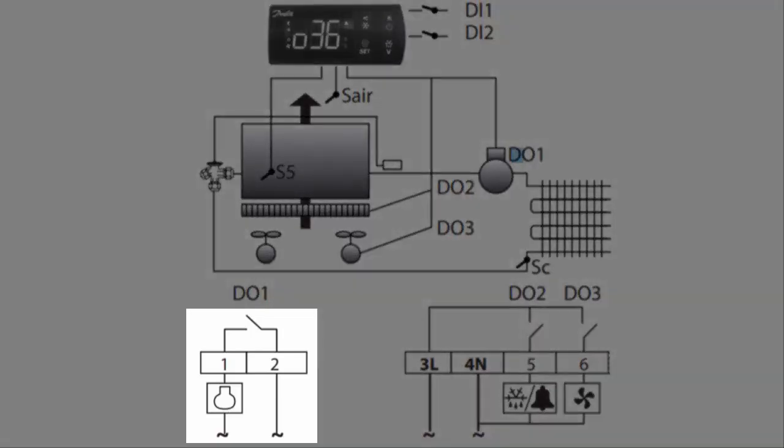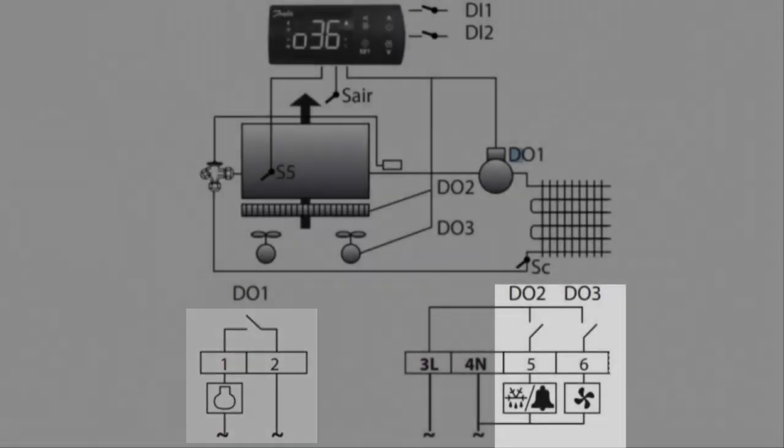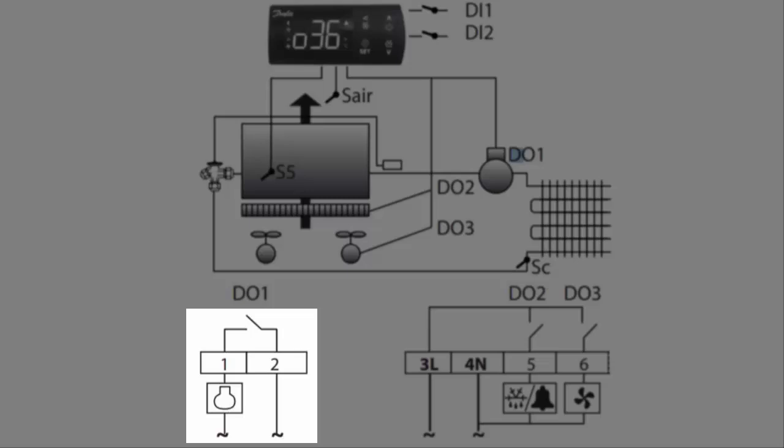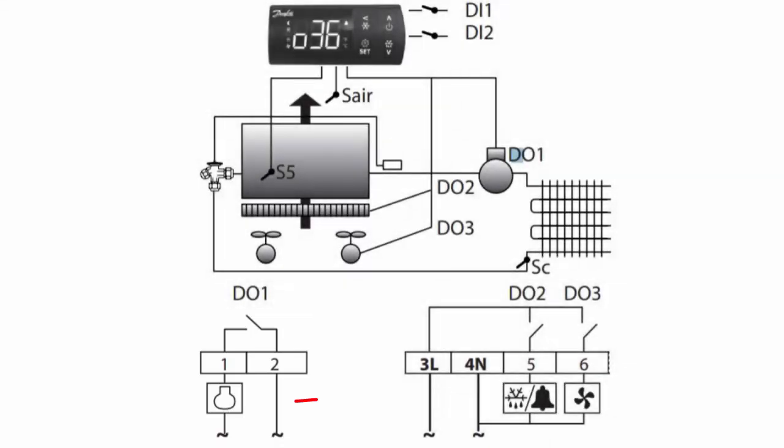First, so you know which is which: DO1 on the left side is a dry contact. Terminals one and two are dry contacts; five and six are wet contacts. Five is used for alarm or defrost - the symbol looks like a melting snowflake. Six is a fan. Here's how this works.